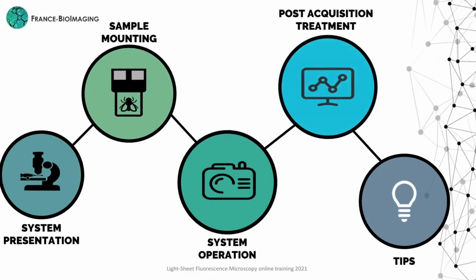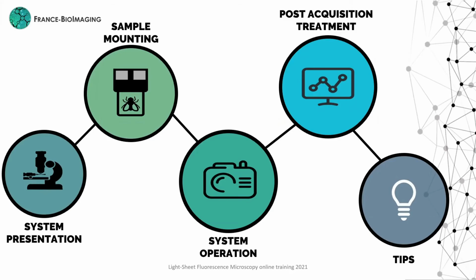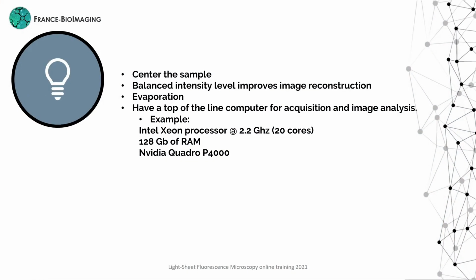Before wrapping up, we'd like to give you a few tips that we hope you'll find helpful if you'll be using this system. We would advise to center the sample in the chamber the best you can. This will avoid losing imaging range due to the objective bumping into the side of the chamber. Better reconstruction will happen if the signal levels are even on both paths. It is possible on Slidebook to balance the laser power and have a live histogram in order to achieve that.